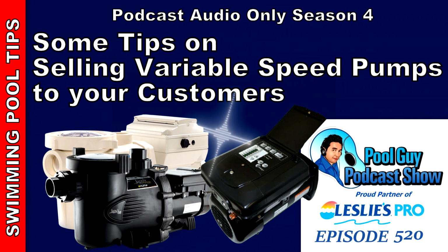Just one side note on the Pentair pumps: if you're going to get the SuperFlo VS, it won't communicate with the automated system. So if you have a Pentair automation, you definitely want to go with the IntelliFlo pump. Even though it's twice the price of the SuperFlo VS, it'll communicate with your automated panel. The SuperFlo VS is mainly a standalone VS pump, not made for automation. So just make that distinction. Because if you look online at the Pentair VS pumps, you may gravitate towards the SuperFlo VS, but just note that the IntelliFlo is the only variable speed pump that will communicate with the Pentair automation at this point.